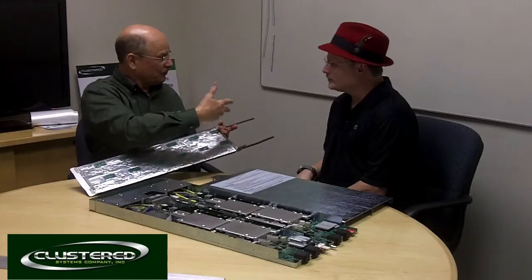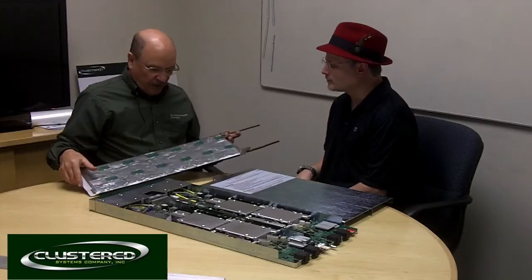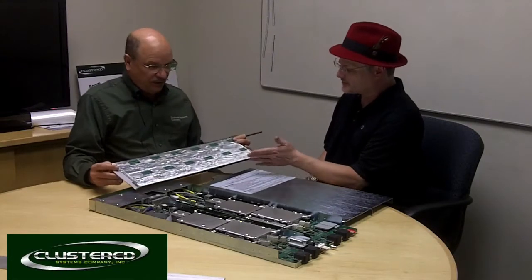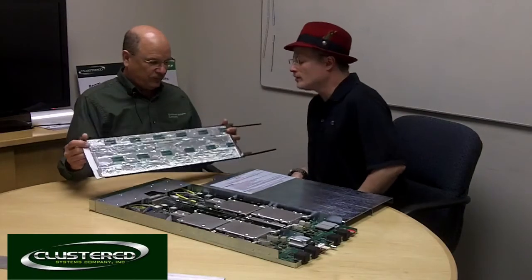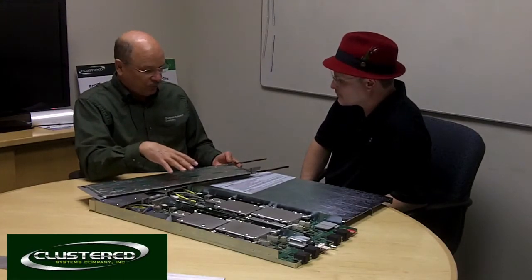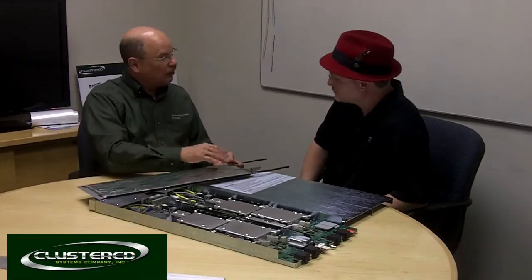When we say steam, it's not your hot boiling water steam — this is cold steam, if you will. It's essentially room temperature, or whatever your chiller temperature is or your heat exchanger outside. This is very efficient; one of these plates can cool up to 1.2 kilowatts of power. Using refrigerant we get very, very good efficiencies. Since we're using the latent heat of vaporization, refrigerant is much more efficient than water. In fact, one of the benefits besides efficiency is it's isothermal — so there's no shadows. Water would warm up as it flows in and out; refrigerant doesn't.